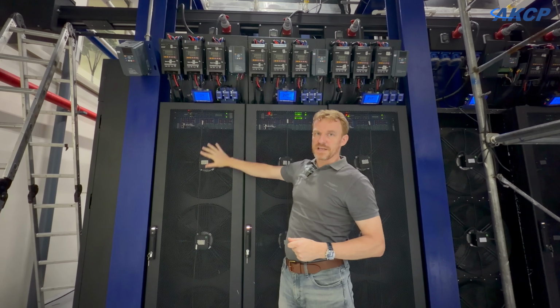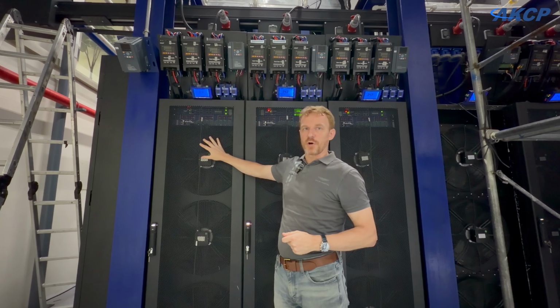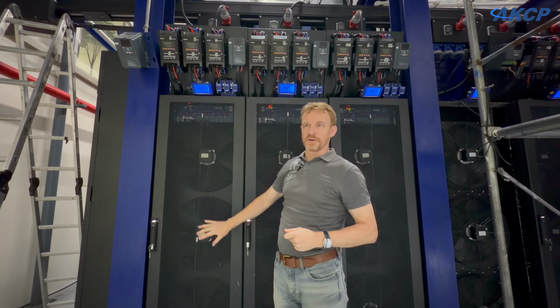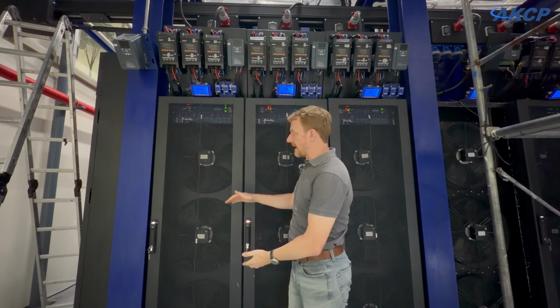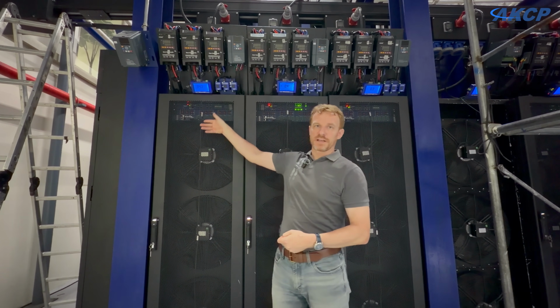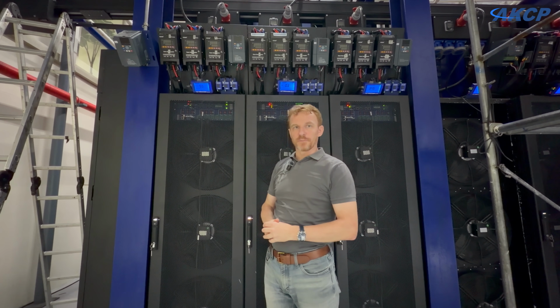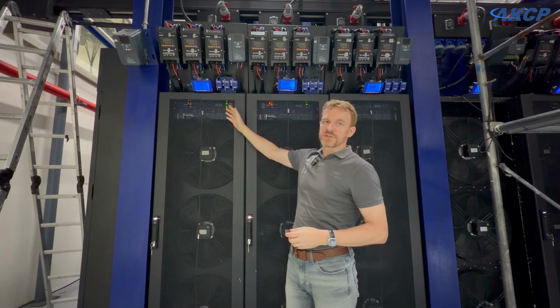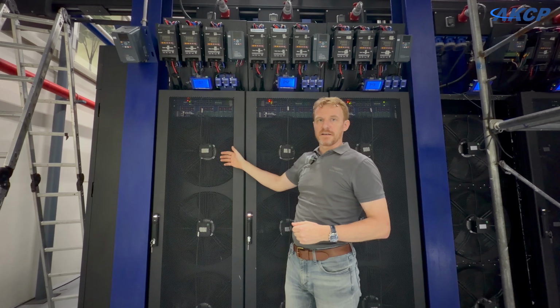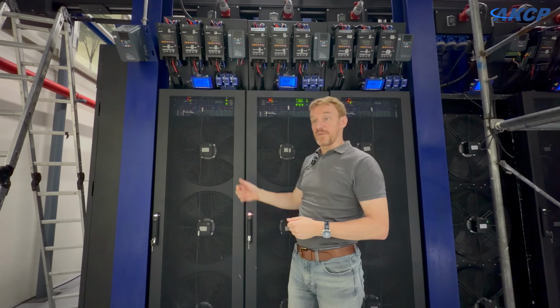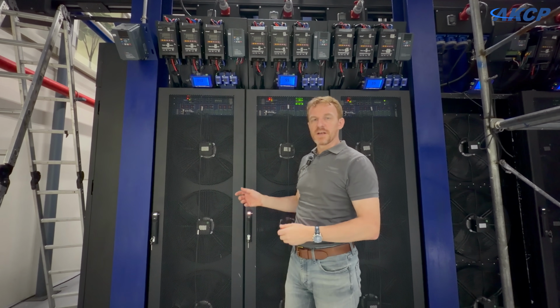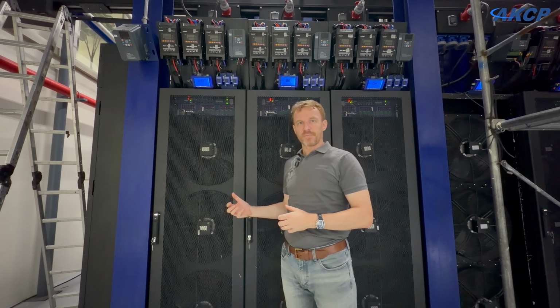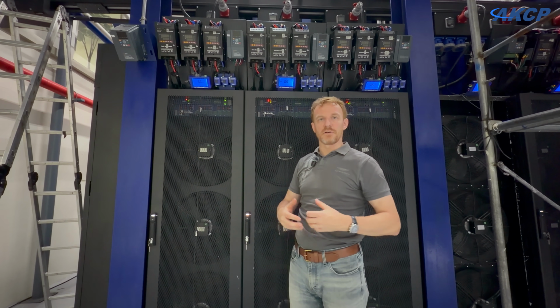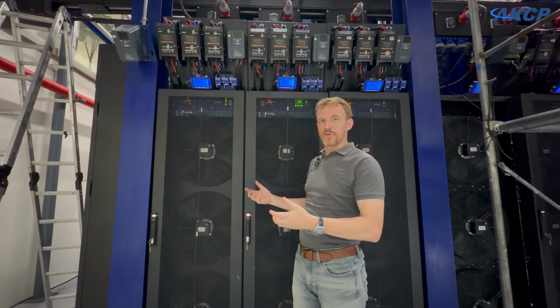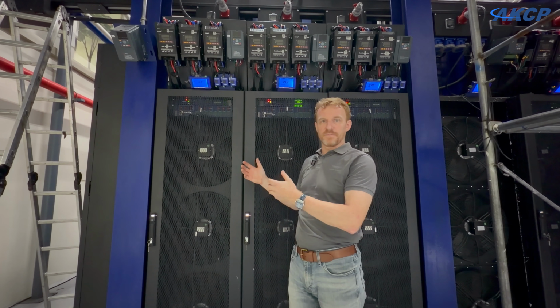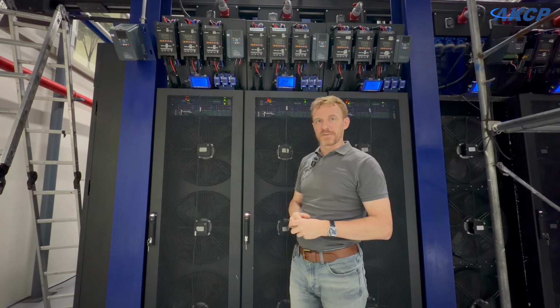So we have 3 heaters in here, 9 kilowatts each, and we can control accurately now the number of kilowatts going to each one. So we could simulate, for example, a rack that had 9 kilowatts of load in the middle and only had 1 kilowatt of load at the top and bottom. We also then have a VFD, which controls the speed to our fans, and we can therefore simulate a fan failure or a fan that's spinning slower than it should. So we can insert faults into the data center, and that allows us to test out our products such as sensor CFD and prove the energy losses and the air leakage that CFD can find.